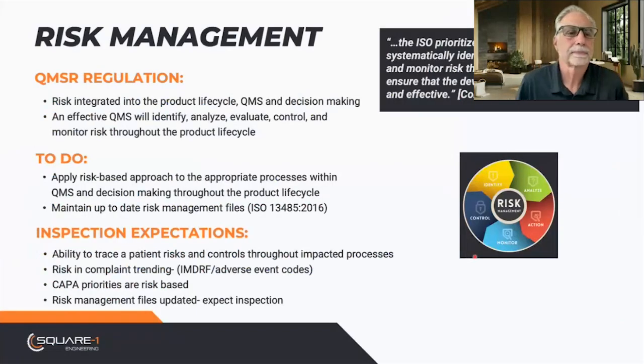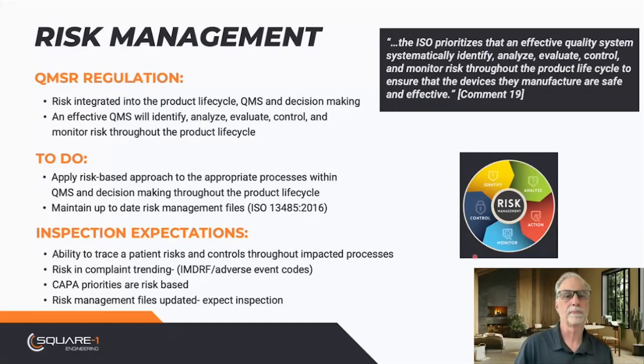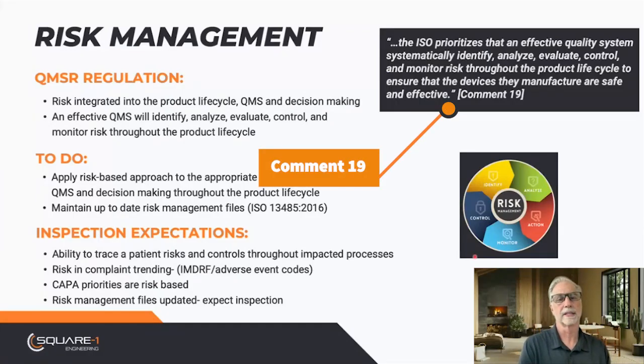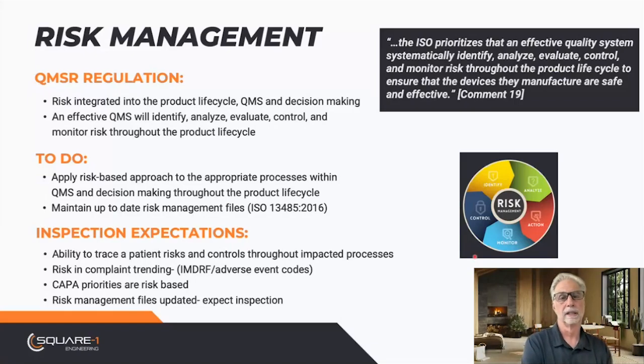So, risk management: the QMSR regulation, what to do, and the inspection expectations. The little box up on the right is in the preamble to the final release of the QMSR, the final rule, and there are roughly 80 pages of preamble. That's really important to get familiar with, just like the preamble for QSIT, because it has a lot of information on how the FDA thinks about things that are important to compliance. So I took this one. This is comment 19, specifically related to risk management. There's also comment 32 that's important.